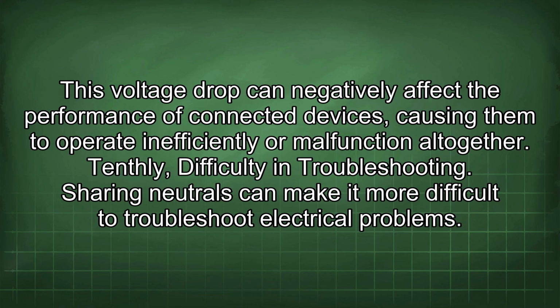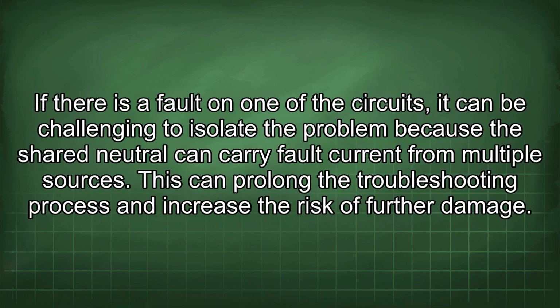Sharing neutrals can make it more difficult to troubleshoot electrical problems. If there is a fault on one of the circuits, it can be challenging to isolate the problem because the shared neutral can carry fault current from multiple sources. This can prolong the troubleshooting process and increase the risk of further damage.